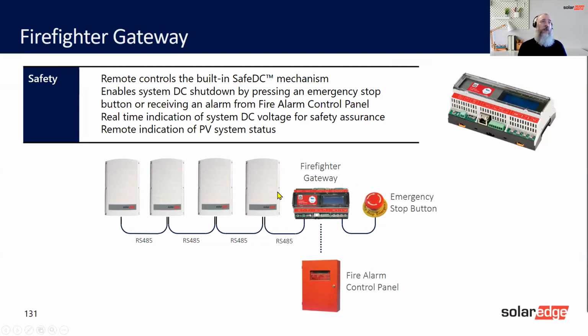What the firefighter gateway does is link to your fire alarm panel and also to an emergency stop. So if you were to discover a fire, you could press the emergency stop and all of the inverters would ramp down, production would be down to 0. There'd still be AC, but production would be 0. That would mean that every single optimizer connected to this site would end up with below 50 volts per string or 1 volt per optimizer.